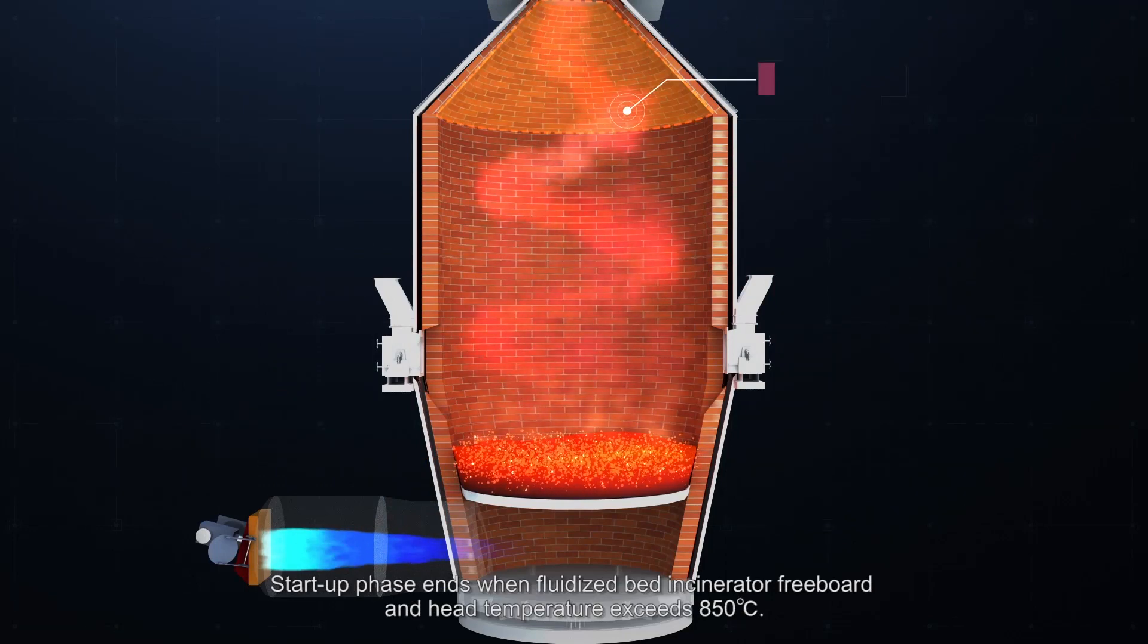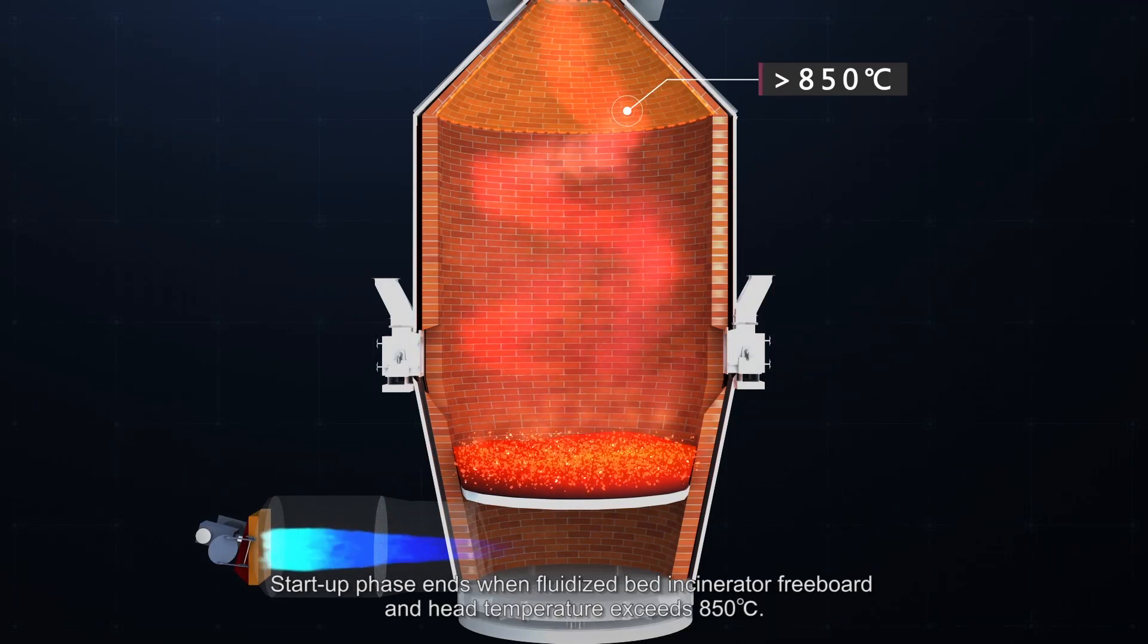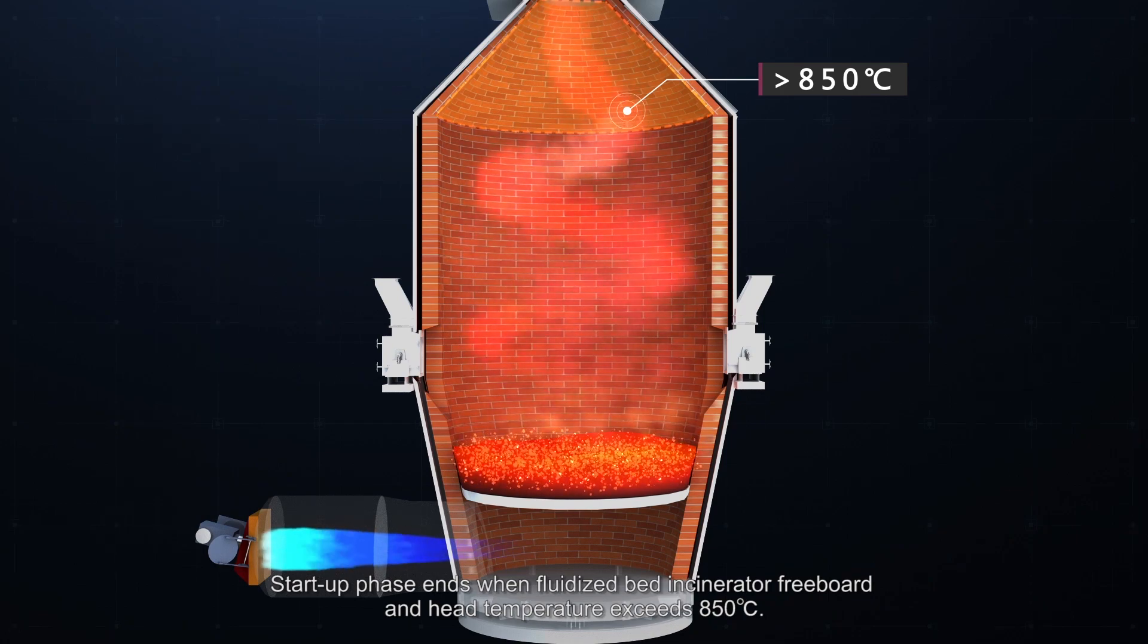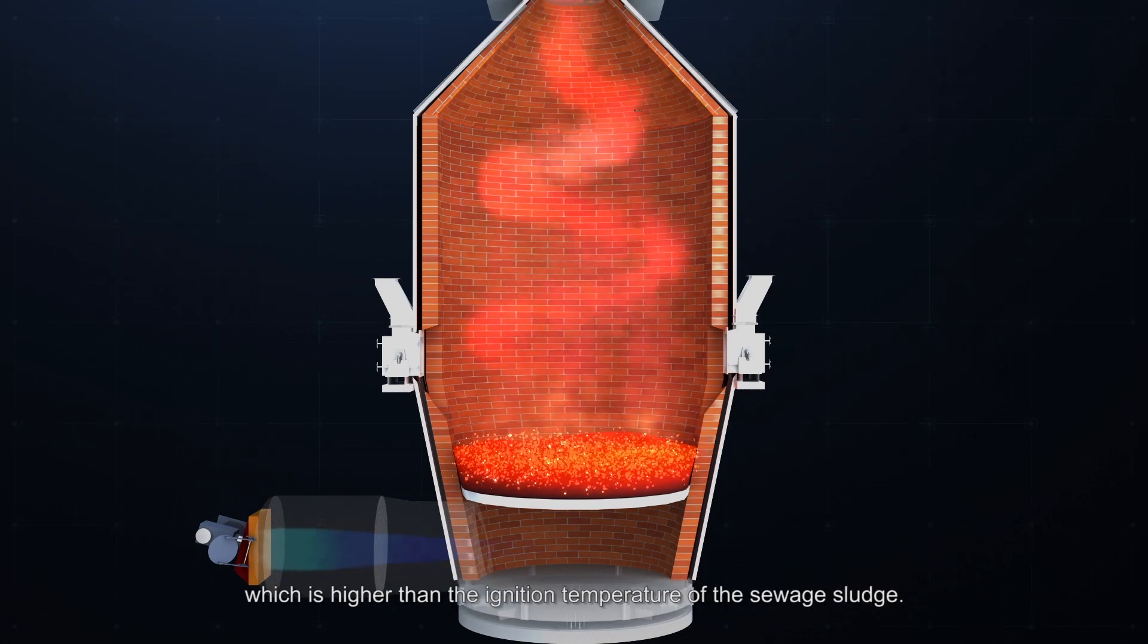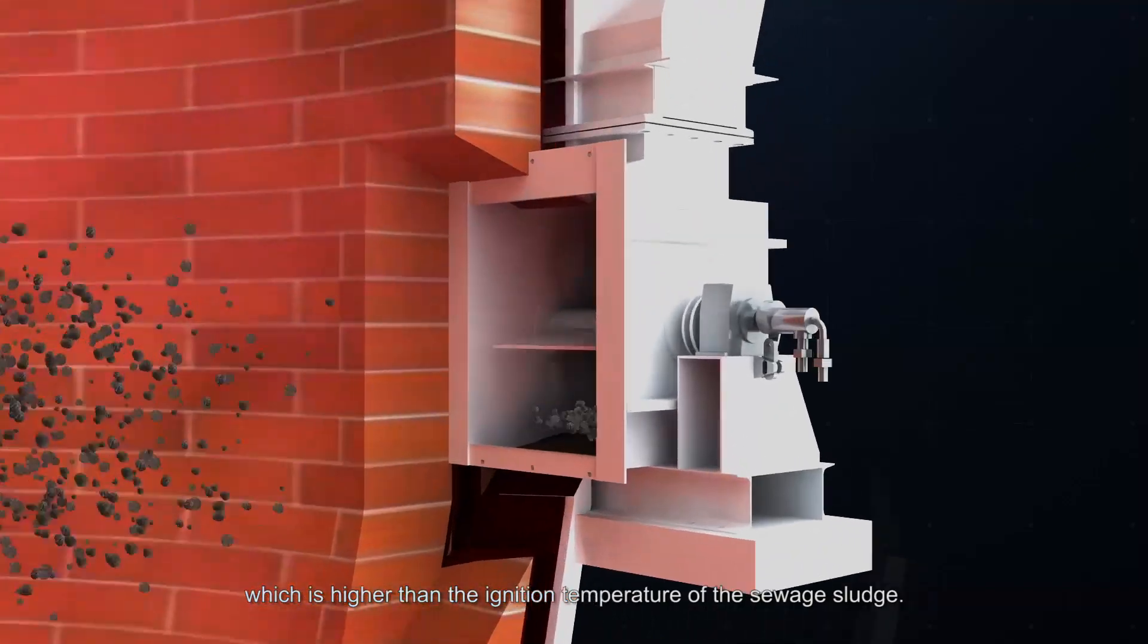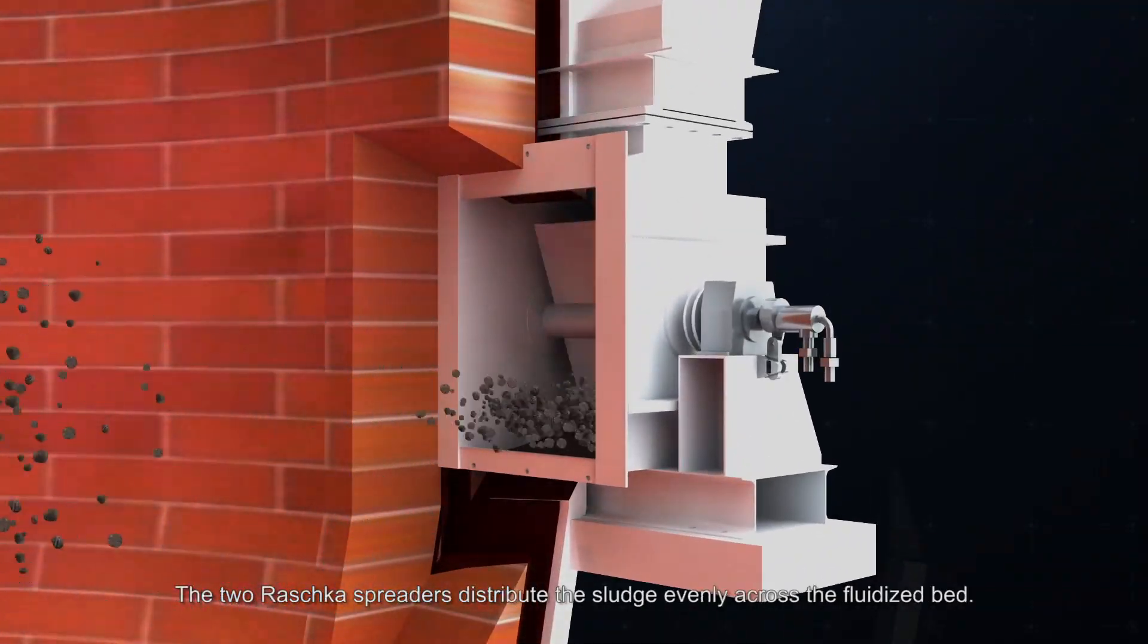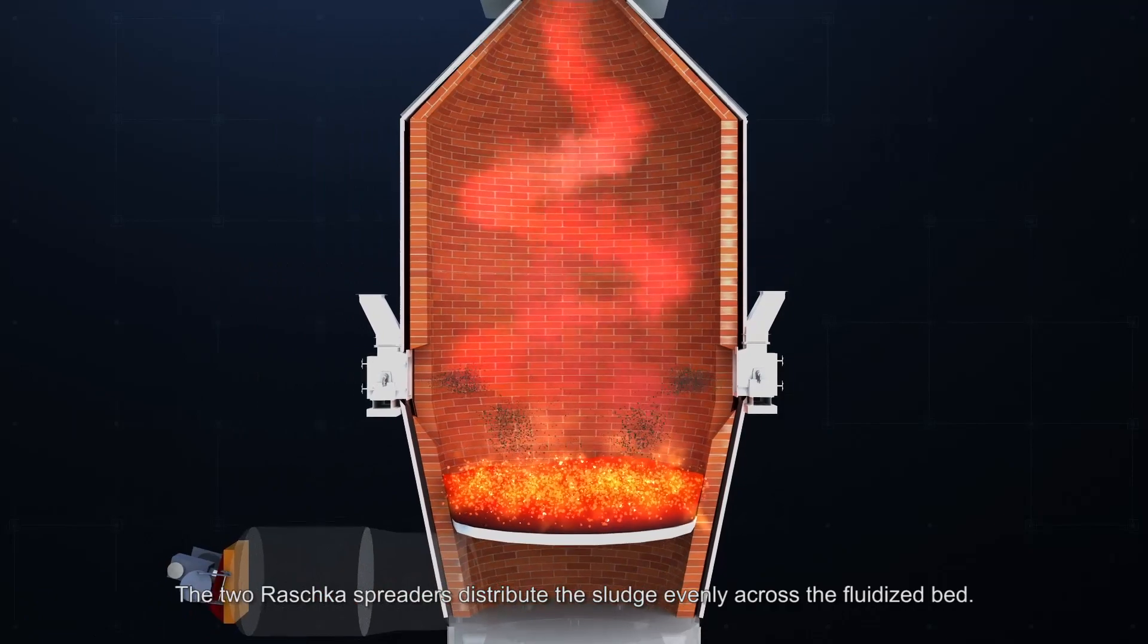Startup phase ends when fluidized bed incinerator freeboard and head temperature exceeds 850 degrees Celsius, which is higher than the ignition temperature of the sewage sludge. The two Raschka spreaders distribute the sludge evenly across the fluidized bed.